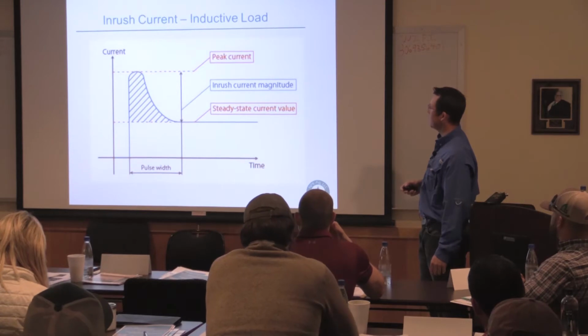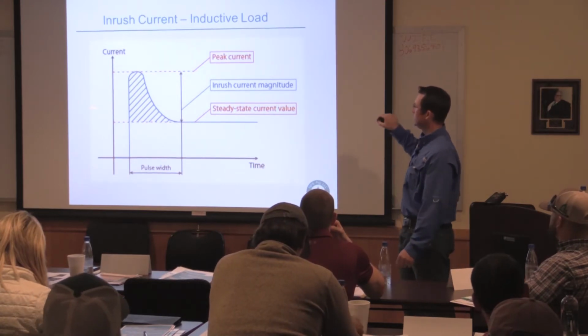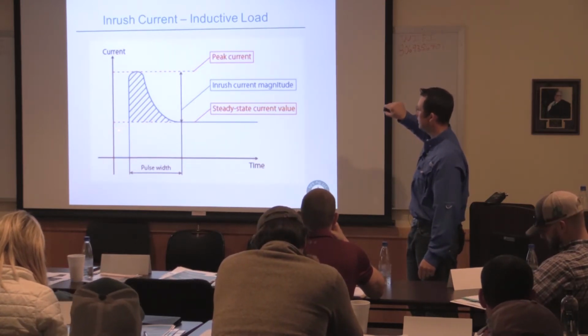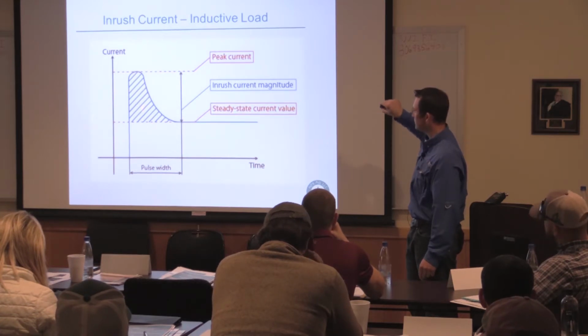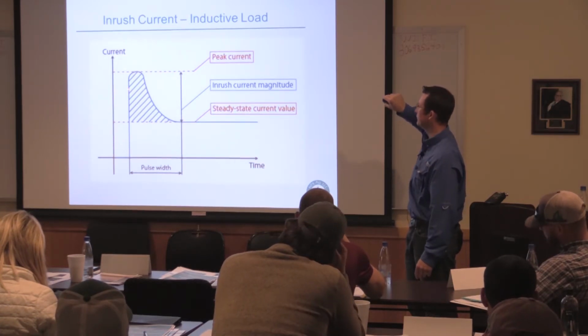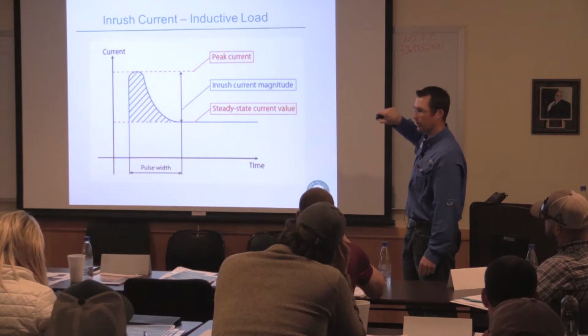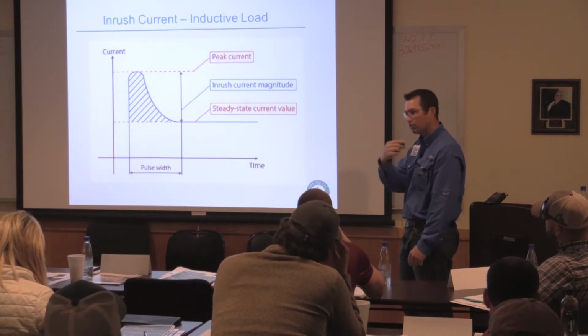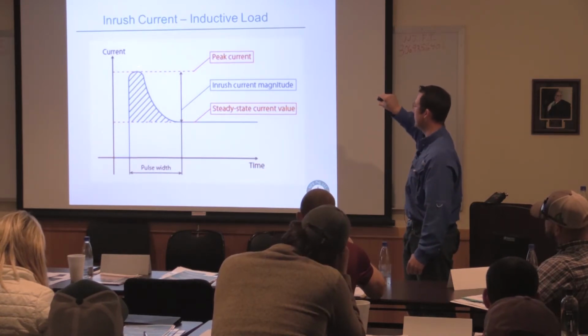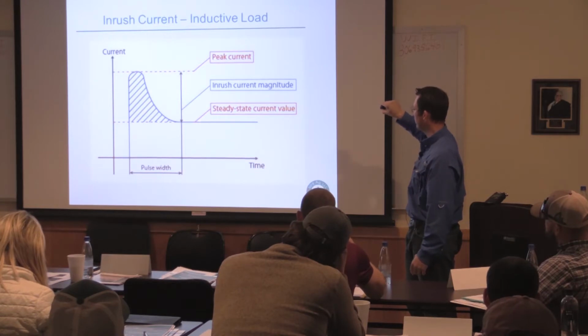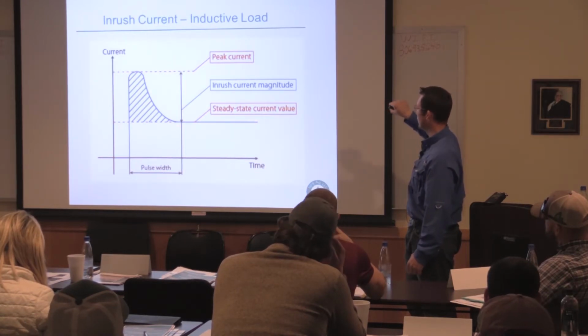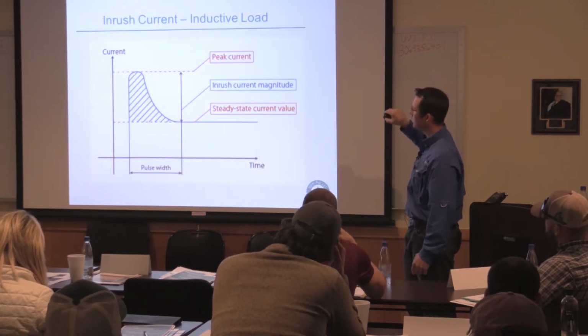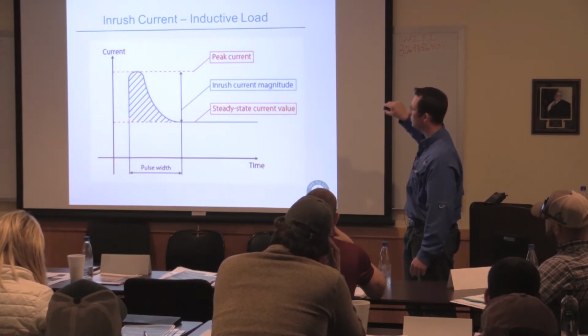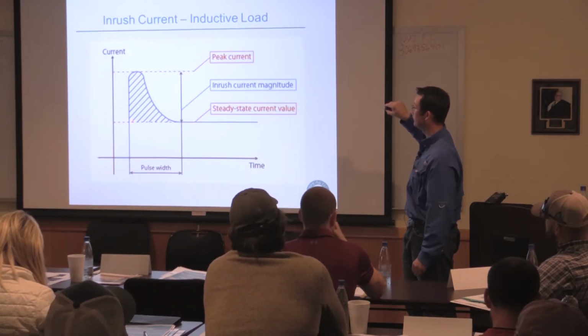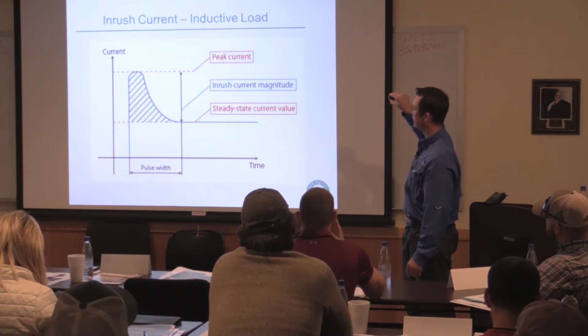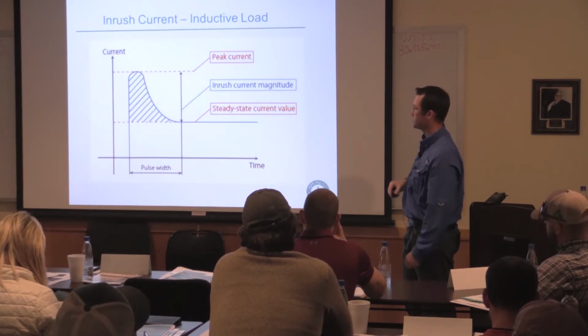So here's the graph to discuss what we just talked about. We're talking about a motor. When it starts, this current, on this axis here, basically goes to infinity, like you're shorting out a circuit. Once that motor starts winding, the current comes down and flows to whatever its steady state value is. Traditionally, you need to design all your electrical wiring, all your starters, all your lines, to compensate for this big spike of inrush current.